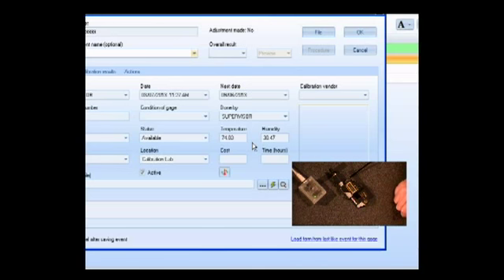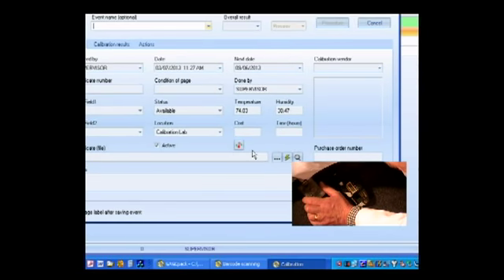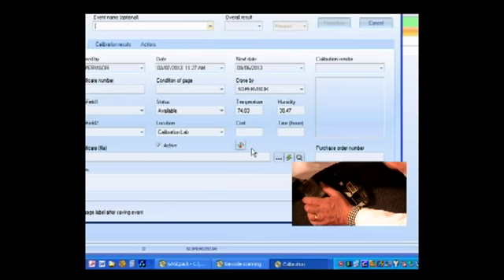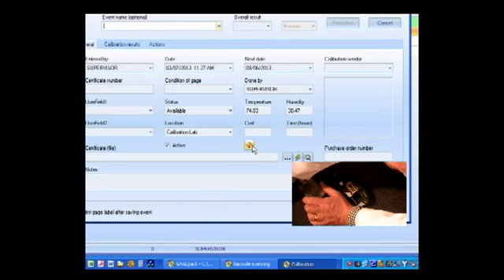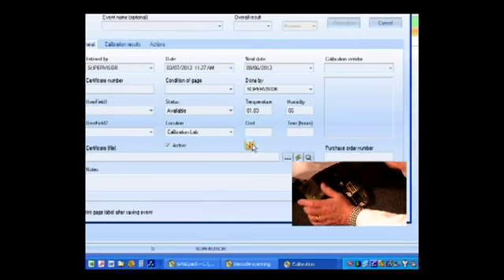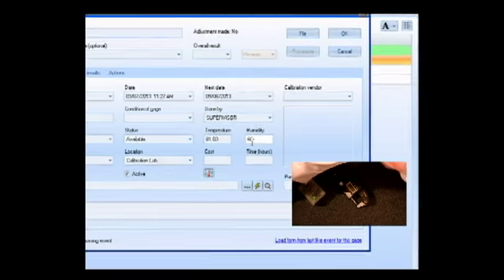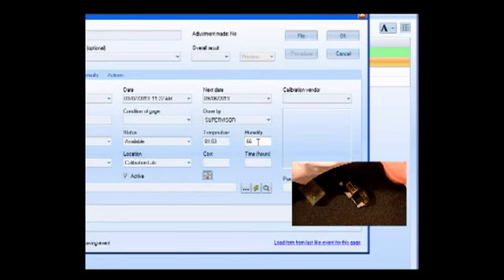So the telephone rang, you got called away, and I'm going to cover the sensor, so we're going to make it get hotter and more humid. The storm just blew in. So you opened this up, you were going to do a calibration. You got called away, or maybe it was time for lunch, and you just left this screen open. Right here on the calibration screen is an update where it'll update the temperature. It went up to 81 degrees, and it's almost raining. It got 66% humidity. Okay.